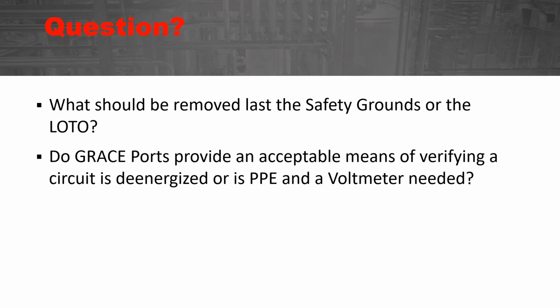This is a great question. I think what should be removed last, the safety grounds or the lockout tagout? So Jay, you want to take a stab on that question? Yeah, that's the lockout tagout. Basically, because if you leave the safety grounds on and you remove the lockout tagout, and somebody decides to close in that breaker, you're going to put a bolted fault on your system, which doesn't make any sense.